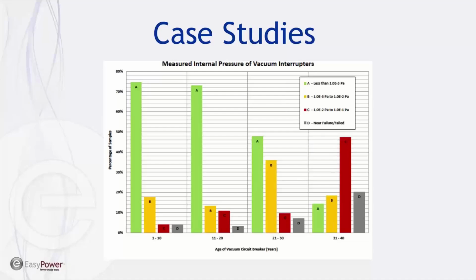So all of these were the exact same type of circuit breaker that were manufactured over this 40-year period. So we were able to test new versions of the circuit breaker, as well as some that were as old as 40 years. And what you see is somewhere between 30 and 40 years, there's a drastic increase in the number of vacuum interrupters that are near failure as well as failed. So this matches well with our experience that the original 20-year shelf life suggested by the manufacturers was pretty conservative, and in reality, these vacuum interrupters can last well over that 20 years. The average now that we're seeing is about 35 years for those original circuit breakers.